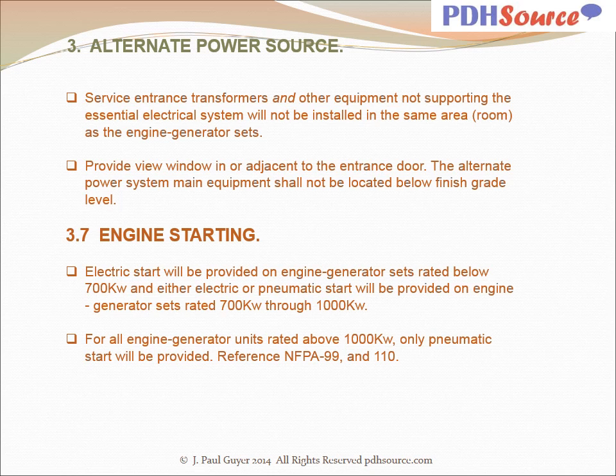With regard to engine starting, electric start will be provided on engine generator sets rated below 700 kW, and either electric or pneumatic start will be provided on engine generator sets rated 700 through 1000 kW. For all engine generator units rated above 1000 kW, only pneumatic start will be provided. Refer to NFPA 99 and 110.